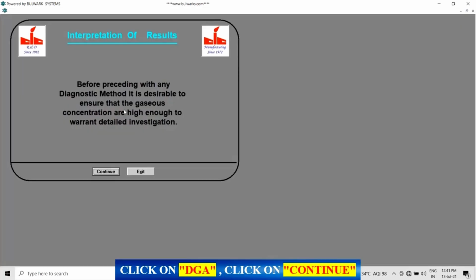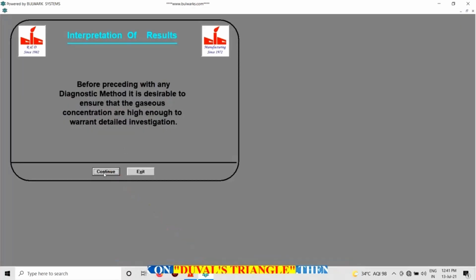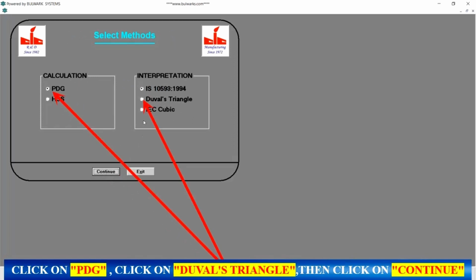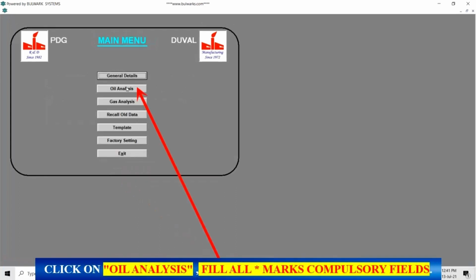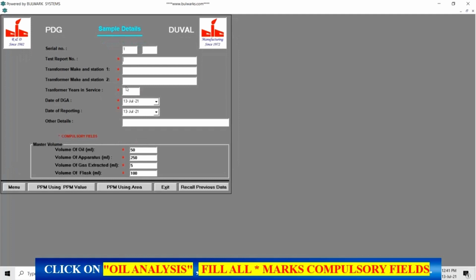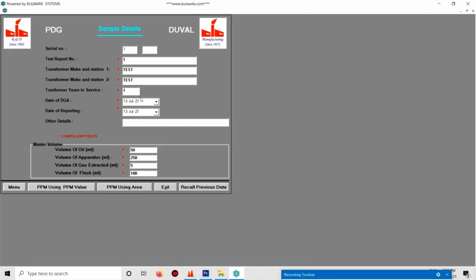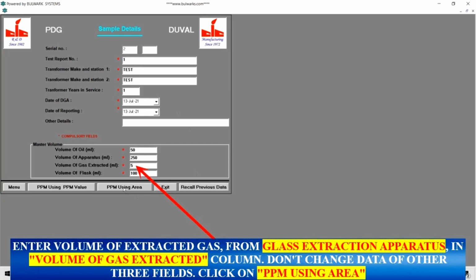Click on DGA, click on Continue. Select PDG and Duval's triangle, then click on Continue. Click on Oil Analysis, fill all asterisk marked compulsory fields. Enter the volume of extracted gas, from the glass extraction apparatus, in the volume of gas extracted column. Don't change data of the other three fields. Click on ppm using area.